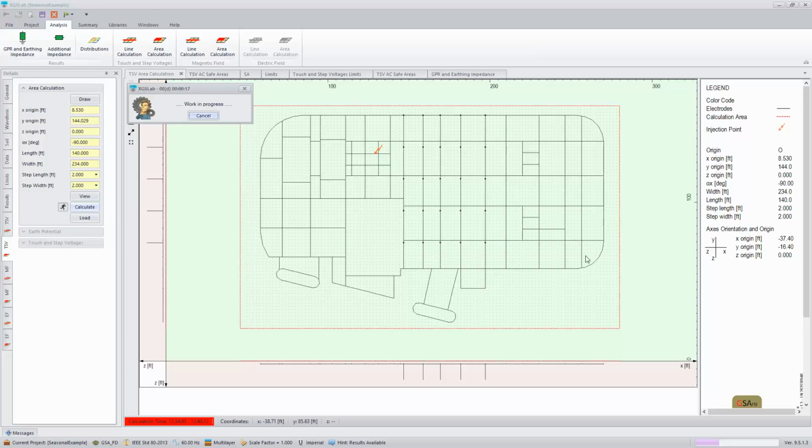We may not see as much improvement to the rest of our system, but just by improving the contact or continuity between the grounding system that isn't affected by our seasonal temperature changes, we're able to ride through and see some performance increase on the rest of our system as well.